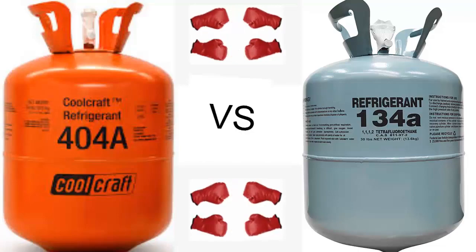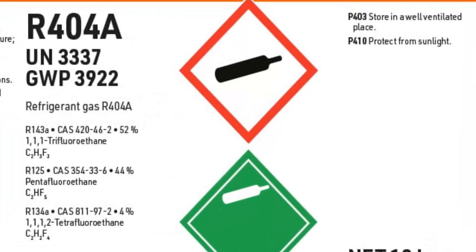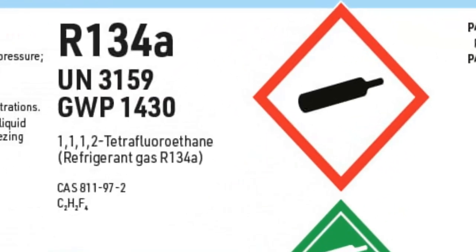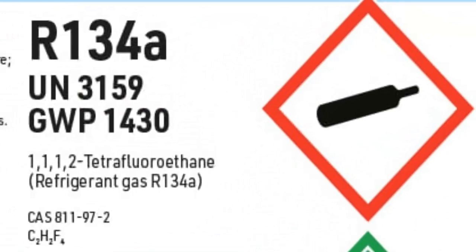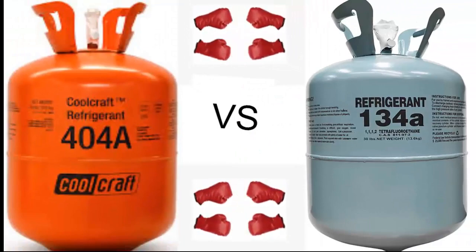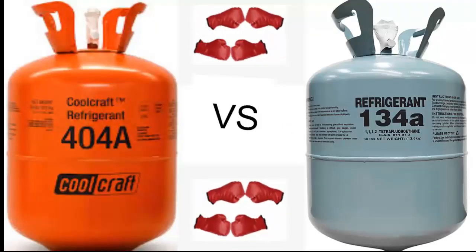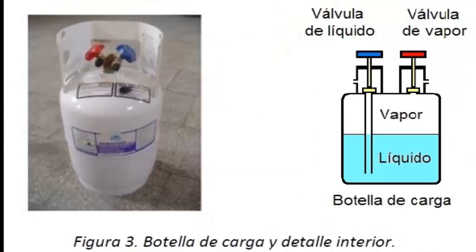Let's start with R404A. This refrigerant is internally composed of a gas mixture, while R134A is a pure gas consisting of a single component. This disparity in composition has a relevant impact on how they are charged in refrigeration systems. R404A must always be recharged in liquid state due to its gas combination, while R134A can be recharged in both liquid and gaseous states without any inconvenience.